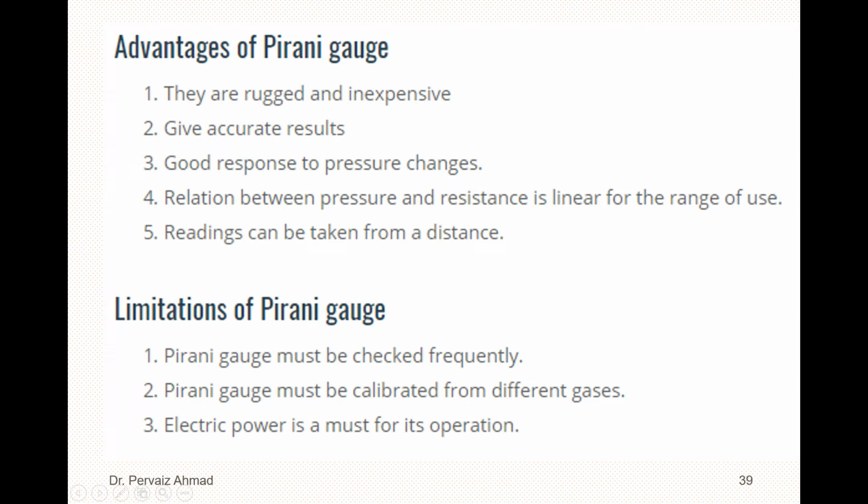There are some gauges where we don't need electrical power; they basically work with the system. But if you want to use a Pirani gauge, remember that electrical power is a must for its operation. So this is all we have for the Pirani gauge and for this section.